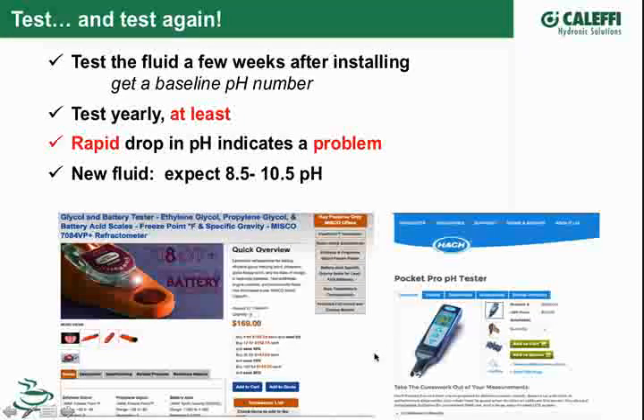Definitely low pH is a clear-cut indicator you have a problem. But pH within that normal range, 8.5 to 10.5, may or may not tell you the whole picture. When metals corrode, they tend to release free hydroxide, which keeps the pH up in the alkaline range. So you can be fooled by pH - clearly if it's acidic you have a problem, but if it's in that normal range you may still have a problem. That's why I go back to visual inspection: if it still looks water white or clear, and the pH is good, that's a real good sign everything is copacetic with your fluid.